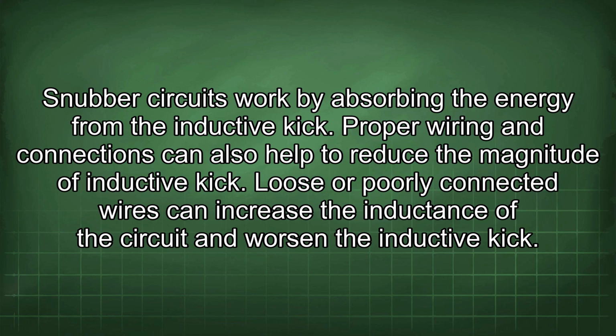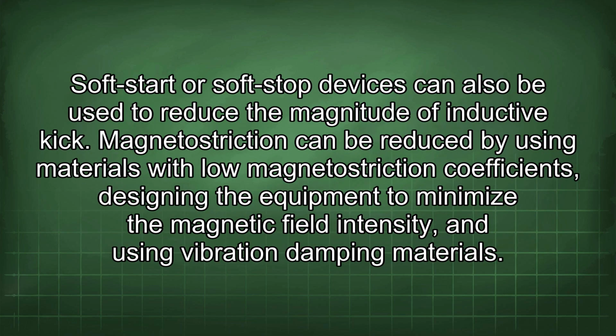Proper wiring and connections can also help to reduce the magnitude of inductive kick. Loose or poorly connected wires can increase the inductance of the circuit and worsen the inductive kick. Soft start or soft stop devices can also be used to reduce the magnitude of inductive kick. Magnetostriction can be reduced by using materials with low magnetostriction coefficients, designing the equipment to minimize the magnetic field intensity, and using vibration damping materials.